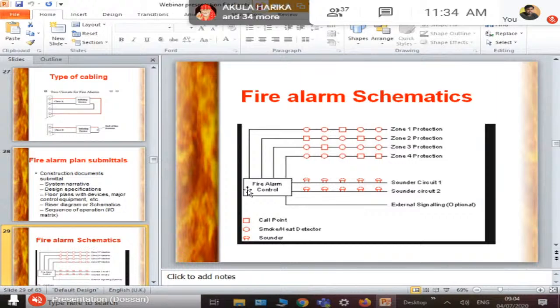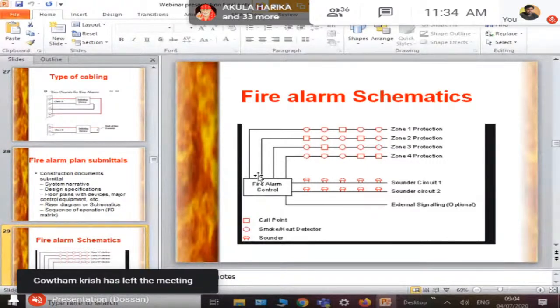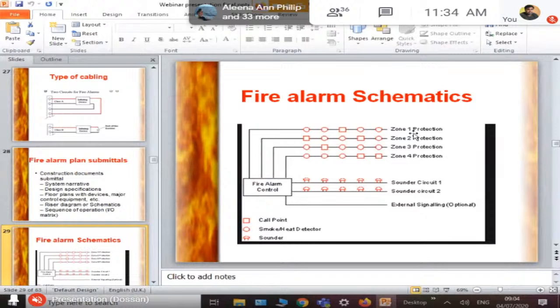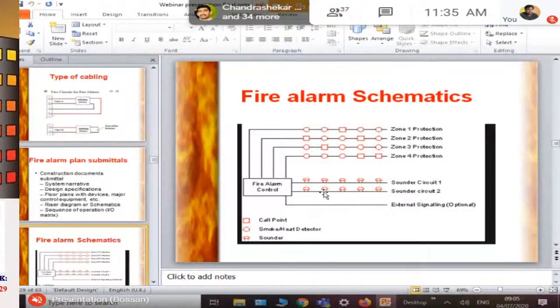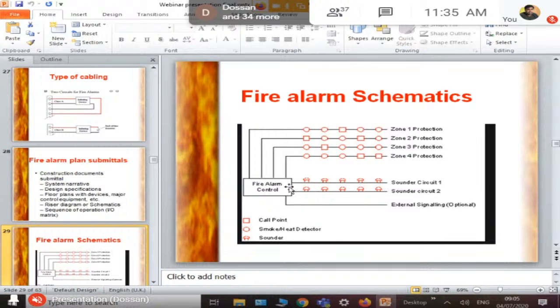So this is a main fire alarm control panel, and from the control panel you will have devices connected in multiple loops. You will have zone separations 1, 2, 3, 4, and you will have devices connected. And the most important thing is that the initiation devices and the secondary devices have to be in separate loops. There is technology now being introduced that you can have the input and output devices on the same loop. Again, it's up to the client to decide if they will use it or not. Okay, so this is schematics, and we'll go to the next slide.